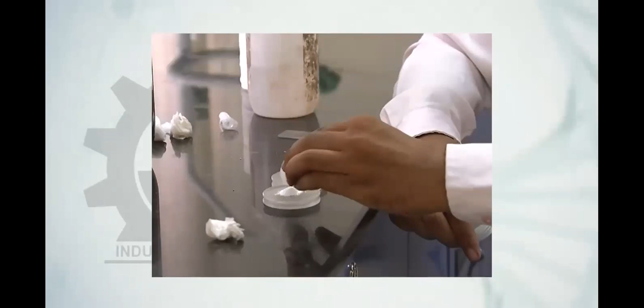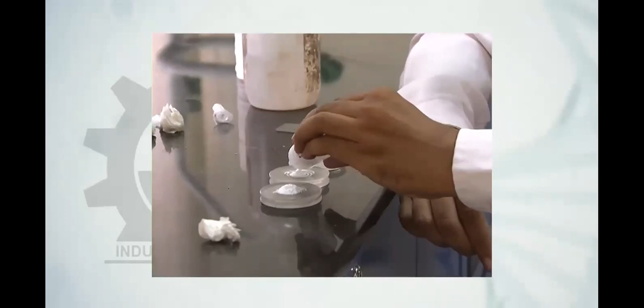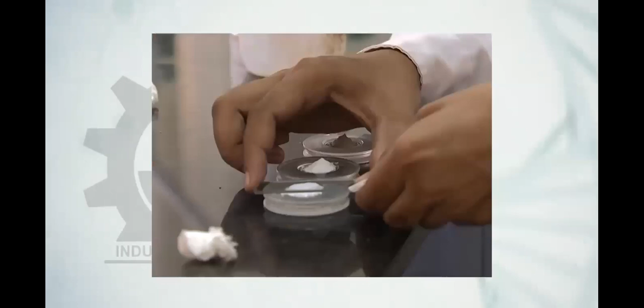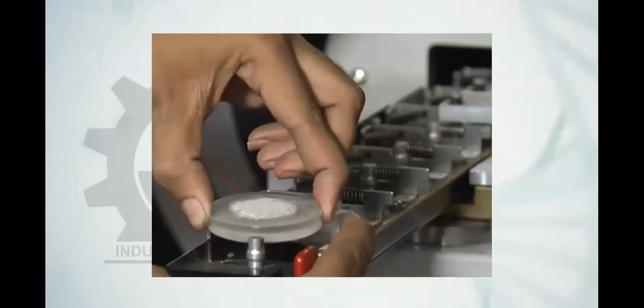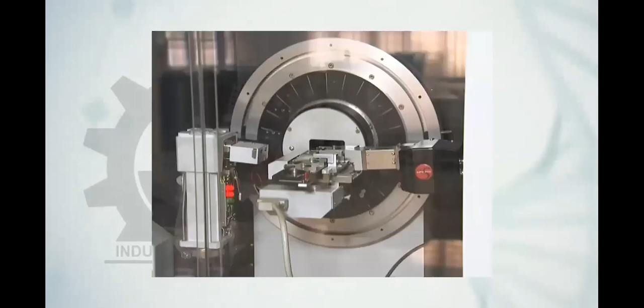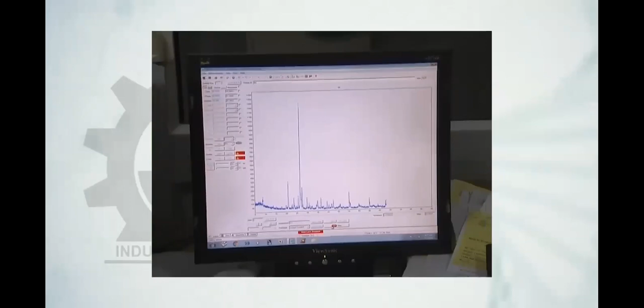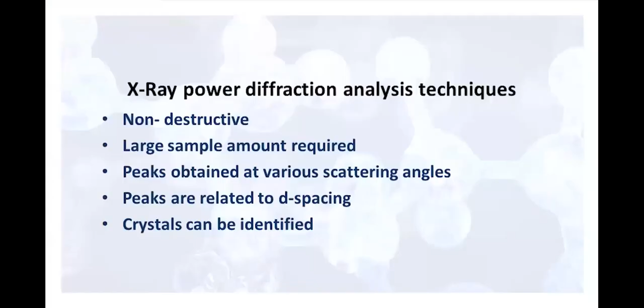The first step of sample preparation is to clean the sampling wells properly. Then the sample is placed in the sample holder. The sample should fill the sample well properly, which can be achieved by using small pressure over the sample holder. Now the prepared samples are placed on the sampling area of the instrument, and the rest of the work is automated. Using software-based controlling, we can vary the parameters of the analysis as per our need and then start the process.